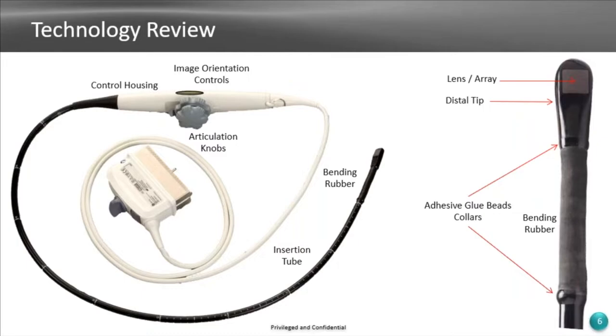After this period, we examine the material. Did it degrade? Did it deform? Did it discolor? And is it biocompatible? Most importantly, you can't just go get some super glue and put it on there because super glue is not biocompatible, and this has patient contact. So we run all those tests, and if we determine that glue survives and doesn't degrade with those cleaners and disinfectants, now it's an approved adhesive we can use.